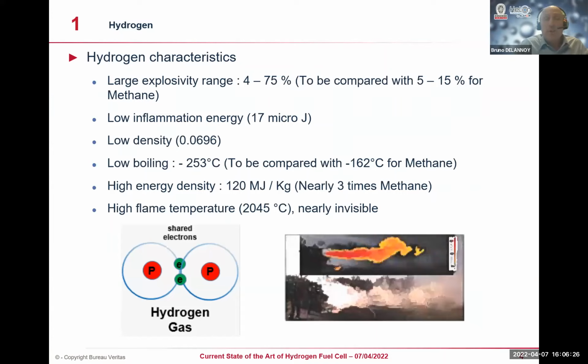So hydrogen is a dangerous gas. There is a large explosivity range from 4% to 75%, compared to methane's 5 to 15%. There is a very low inflammation energy, 17 microjoules, so very small - it is a very dangerous gas. The ATEX characteristic is 2CT1. But the advantage is that this gas is very light, meaning it will dissipate and dilute very quickly in air. So this is a big advantage.